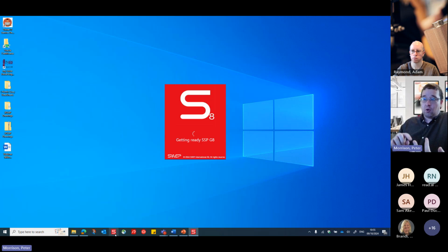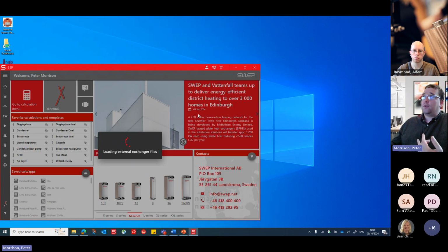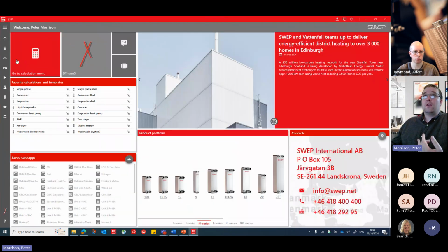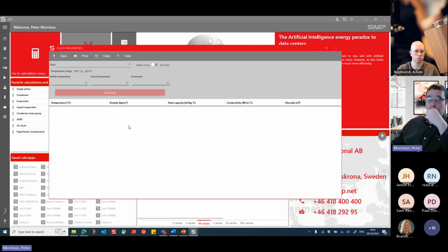With calculations, things you need to remember are you need either the inlet or the vapor quality. Either one of them can work. You need to know the evaporation temperature. If you don't know that, you can find it using fluid properties, in the fluid editor.